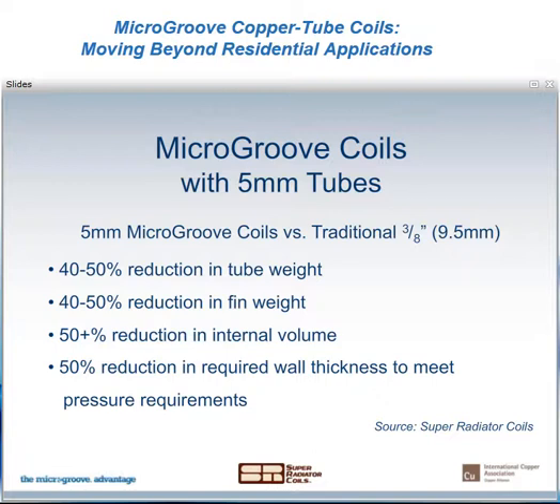Smaller diameter tubes can also support pressure with thinner tube walls than the larger tubes can, and again, this leads to significant material reductions. And if we look at this pressure benefit a different way, with smaller tube diameters, we can handle much higher operating pressures with the same wall thicknesses that we had in the larger tubes. And this is particularly exciting to engineers that are working with CO2 systems.